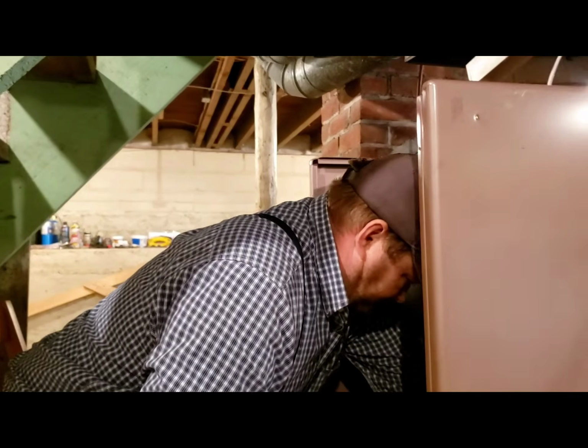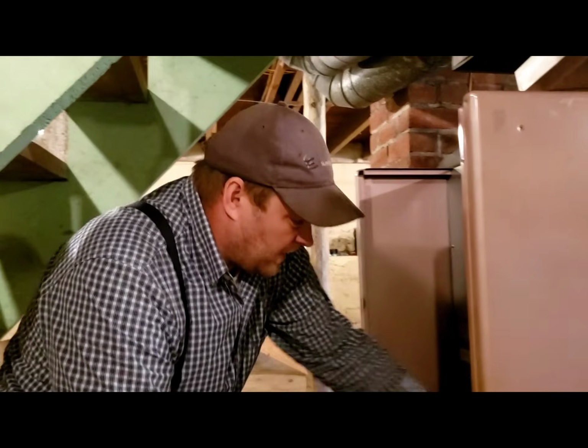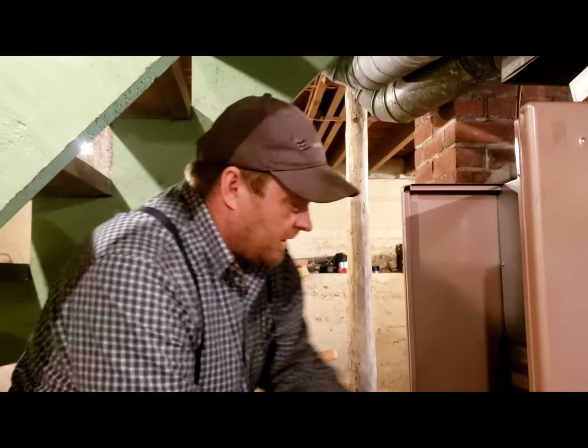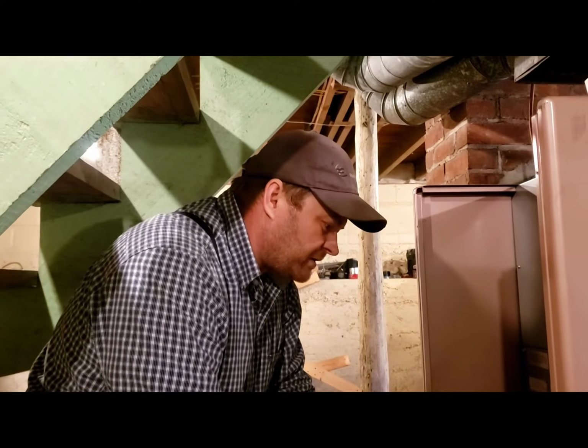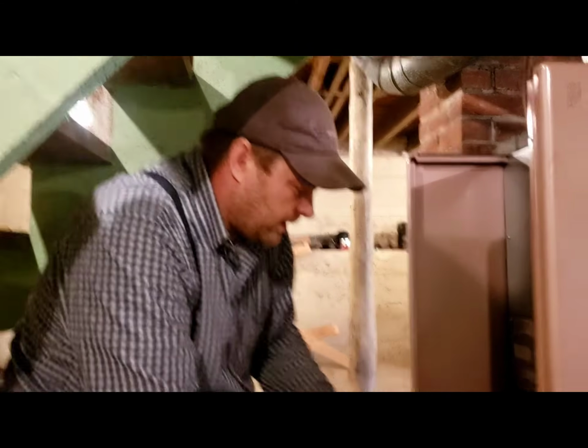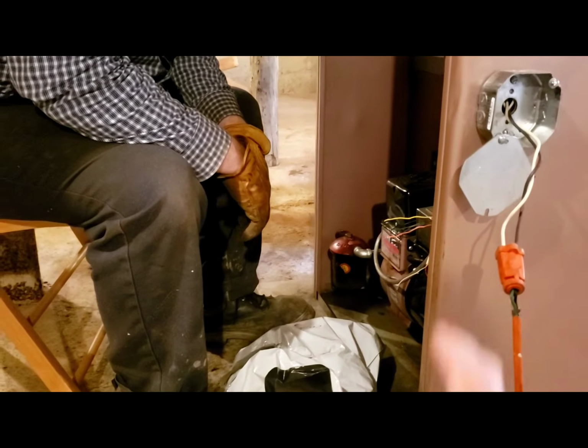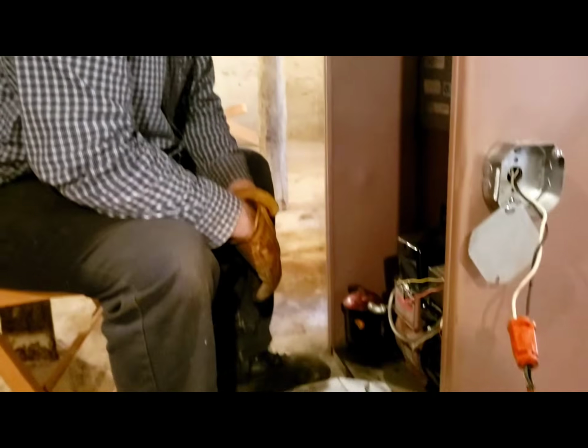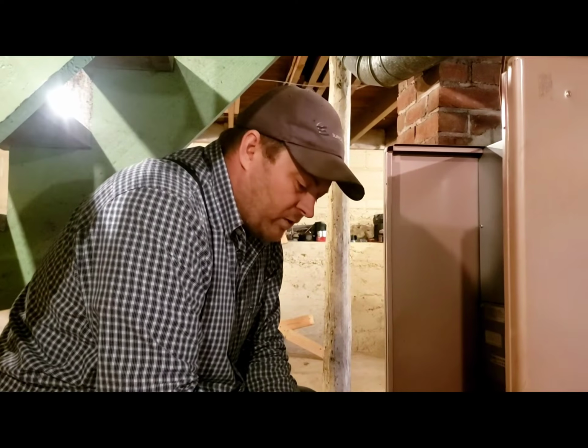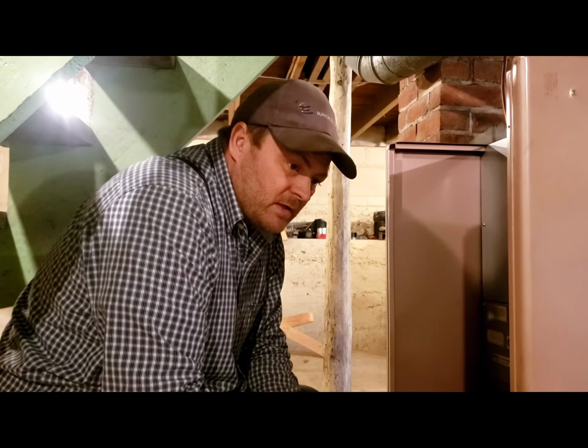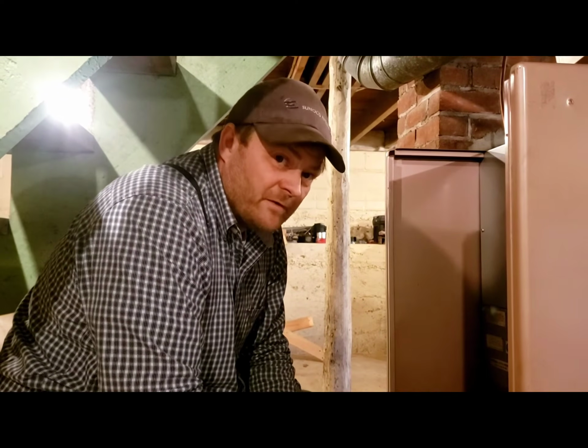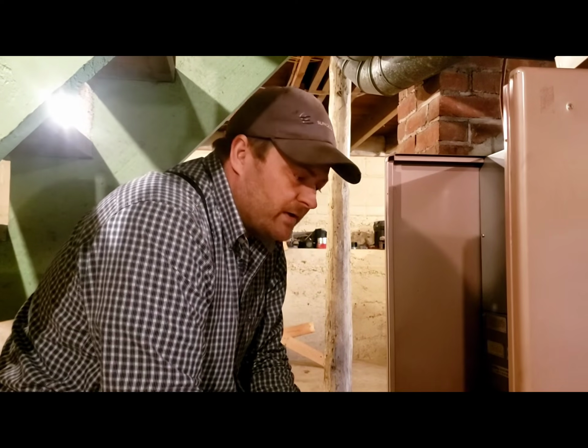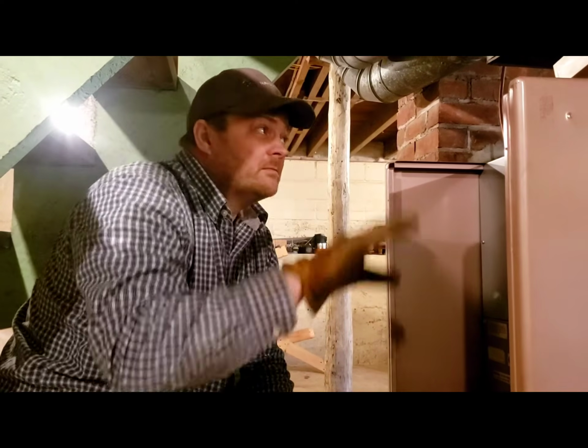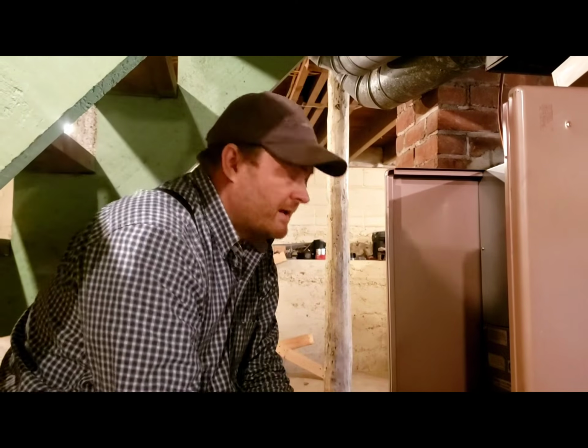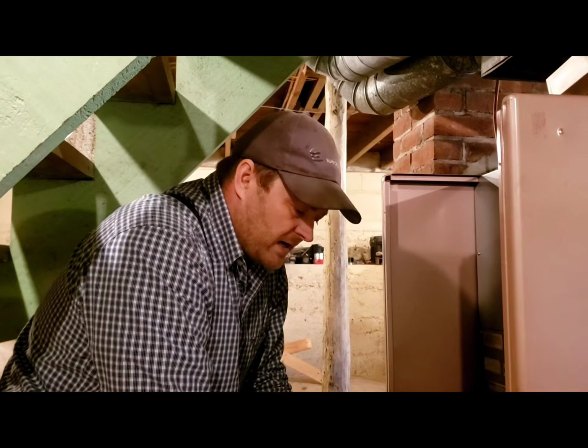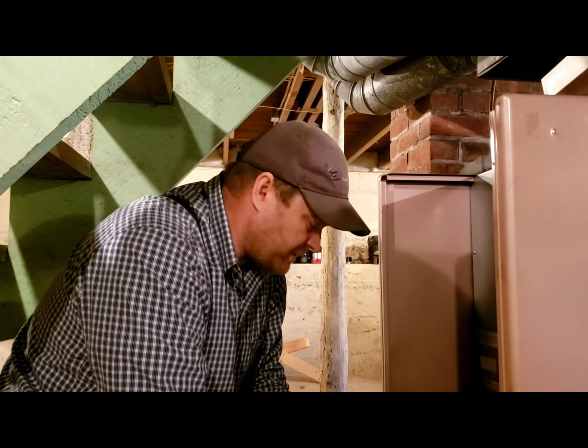So what would you normally do in that yearly service? Change the filter from the tank. This tank at this house is in the garage, so I don't ever like filters out. If your tank's in your basement, put your filter on your tank away from the burner. Sometimes I've mounted them on a wall on a nice bracket. But if your tank's in your garage, or if your tank's buried, you have no choice.